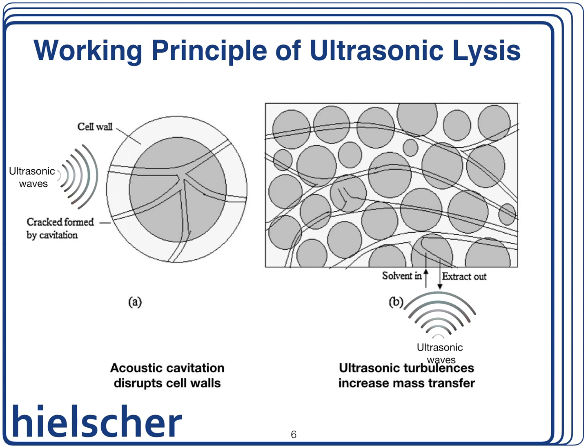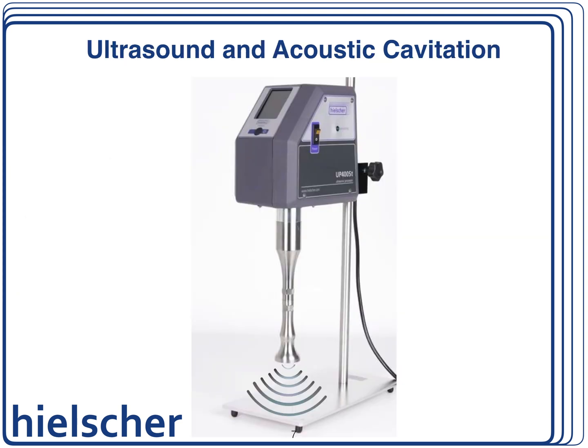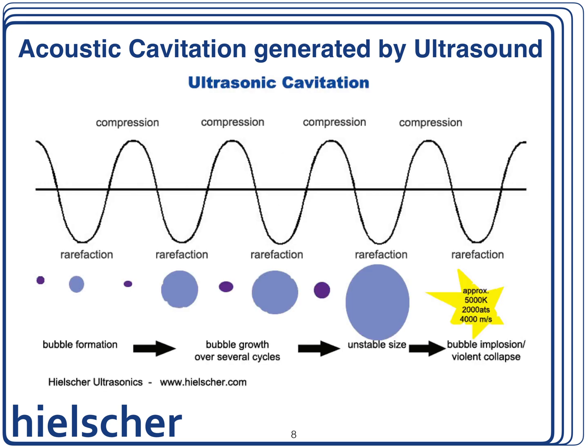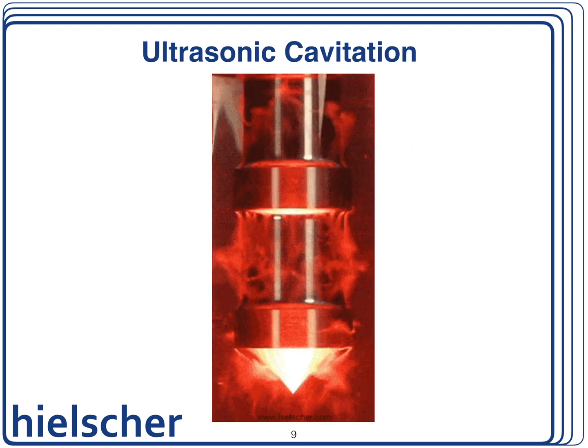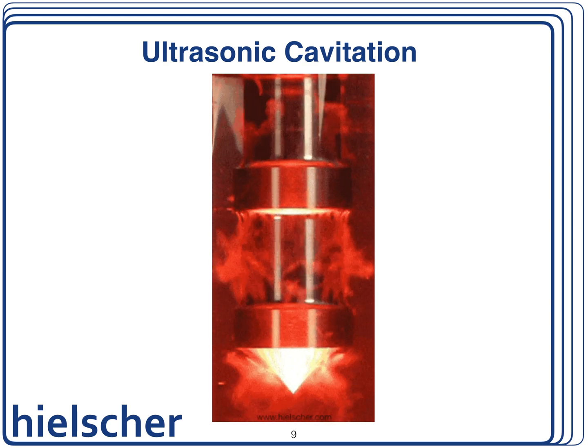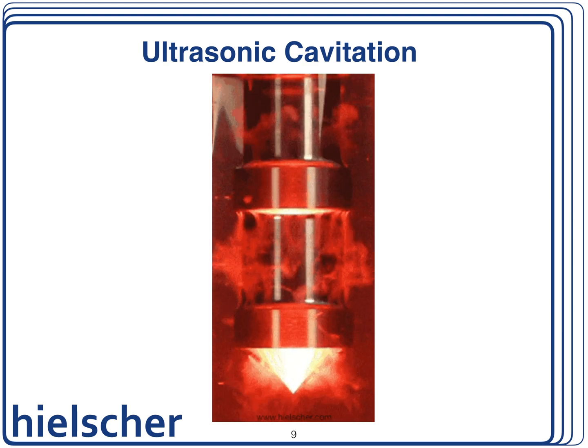Now let's dive into how a sonicator operates. Imagine a sonicator as a transmitter of ultrasound waves. It sends these waves through a probe or sonotrode into a liquid. These waves create alternating high and low pressures, making small bubbles in the liquid. These bubbles grow and collapse, a process called acoustic or ultrasonic cavitation. This collapse generates energy shock waves, microjets, temperature differentials, and pressure shifts in the liquid.